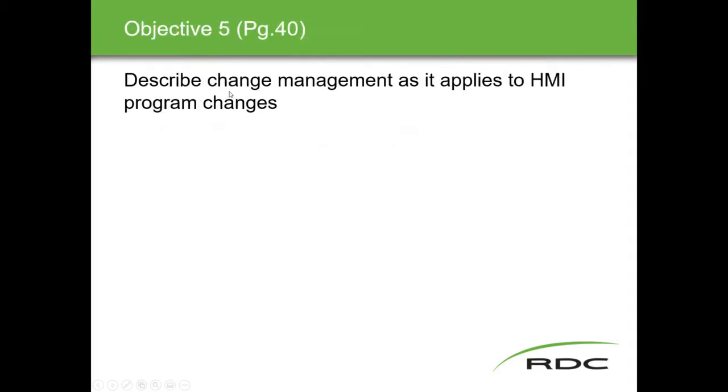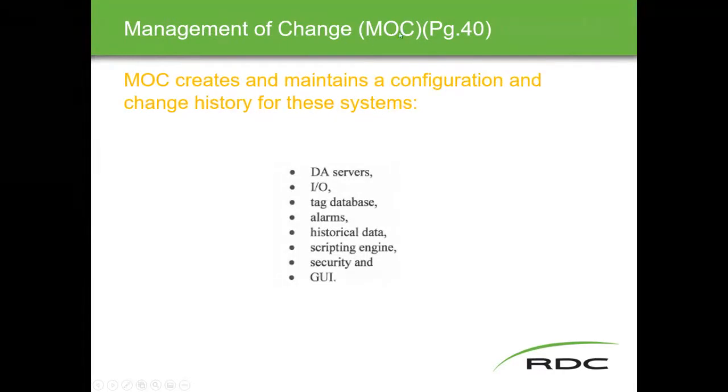Objective 5, change management. Again, very similar to change management when we talked about PLC program changes. It applies similarly to HMI program changing. Management of change, or MOC, is there to create and maintain a configuration and change history for these systems. And these systems, as you will see, are all the subsystems associated with HMIs: the data server, the IO subsystem, the data tag database subsystem, the alarm subsystem, the historical data subsystem, the scripting engine subsystem, the security subsystem, and finally the graphic user interface.